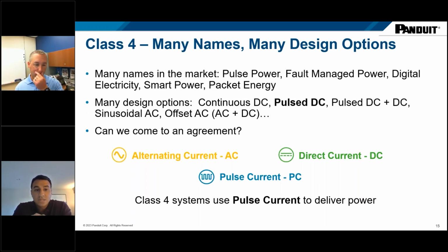But there are also many ways to design a class 4 system. Whatever you have running through the cable could be a continuous DC, it could be a pulse DC signal, it could be AC. There's really no limitation on how you design a class 4 system. What you really need to worry about, though, is being able to detect the faults that are listed in the standard and be able to detect them quickly.